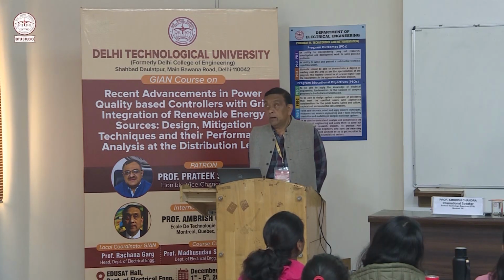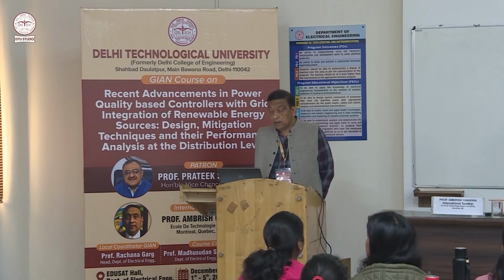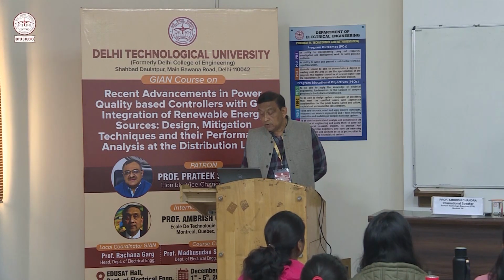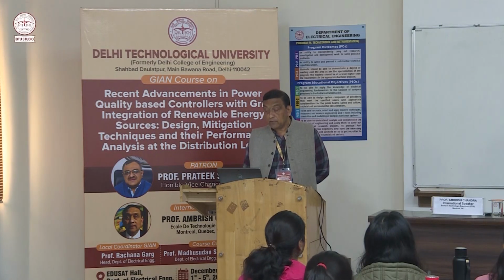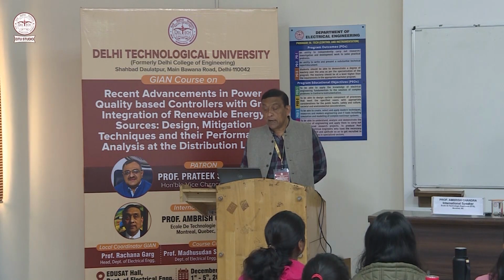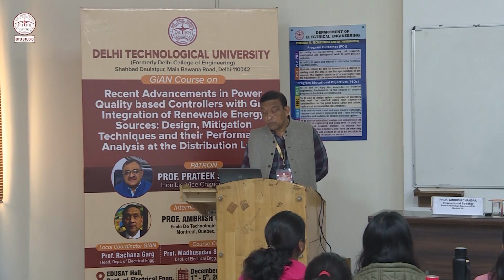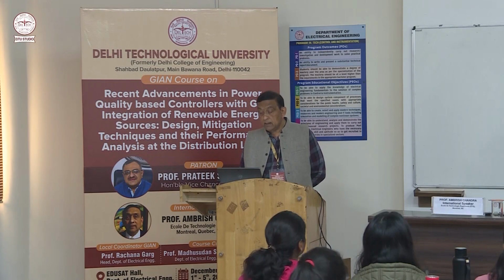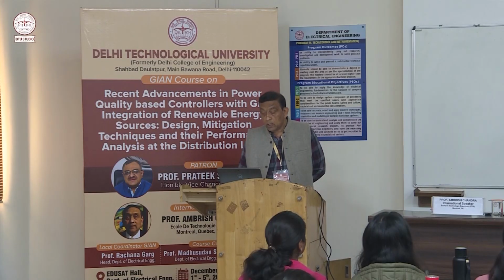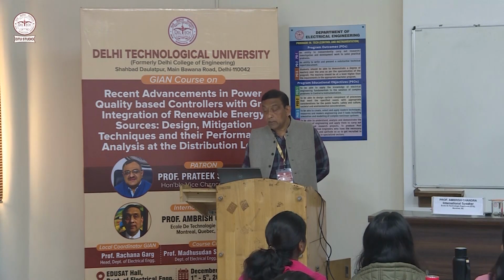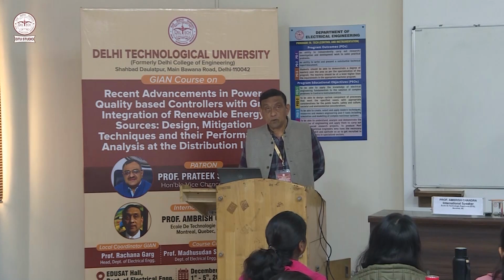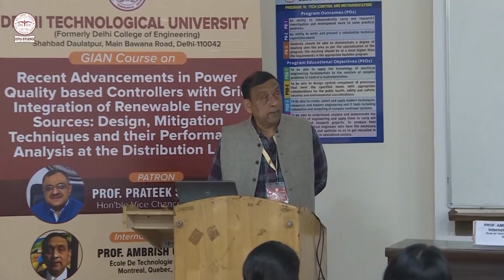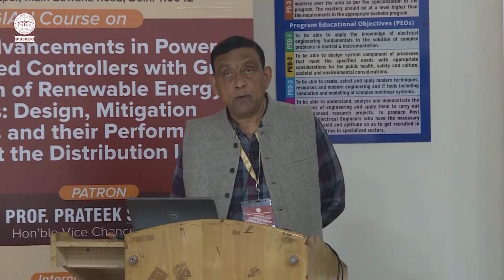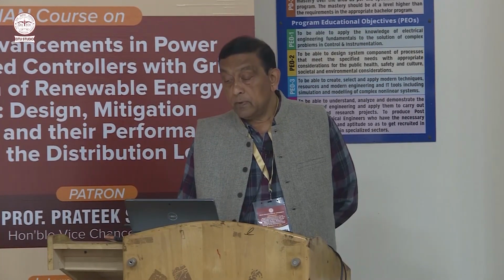Then we discussed the different issues: impulsive transients, impulsive overvoltage and oscillatory transients. Then voltage sag or dip for a few cycles, and what problems voltage sag may cause. Examples of voltage sag are a single line to ground fault, or a large motor starting, which draws a lot of current, 5 to 6 times the nominal or rated current of the machine. So it causes a huge voltage drop across the impedance of the line.